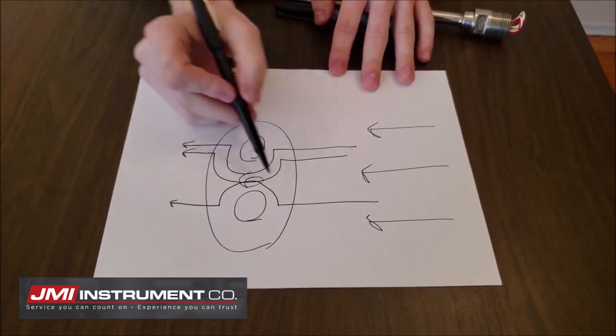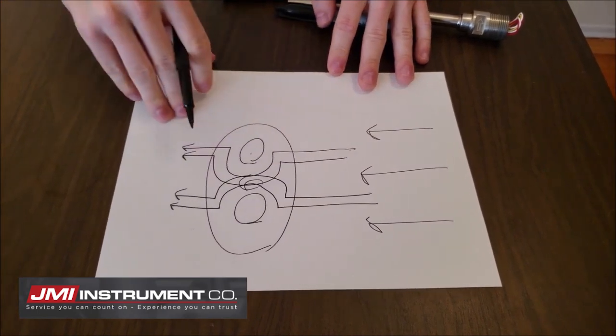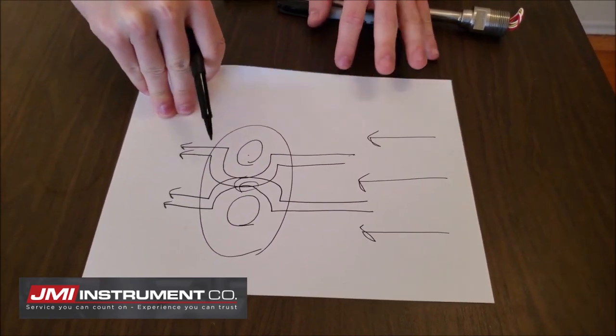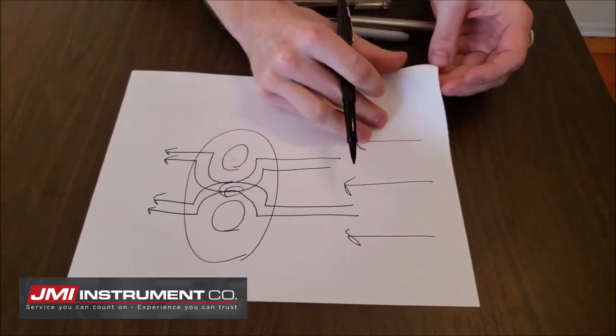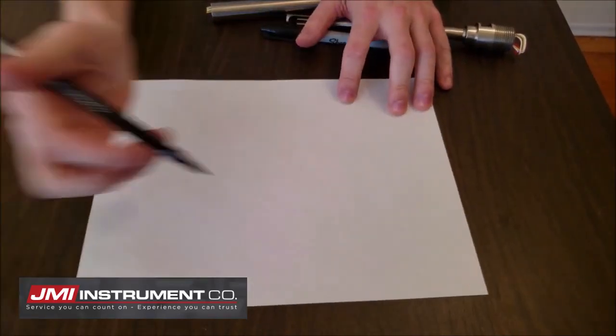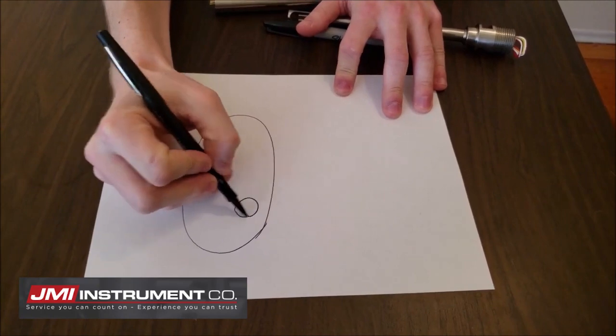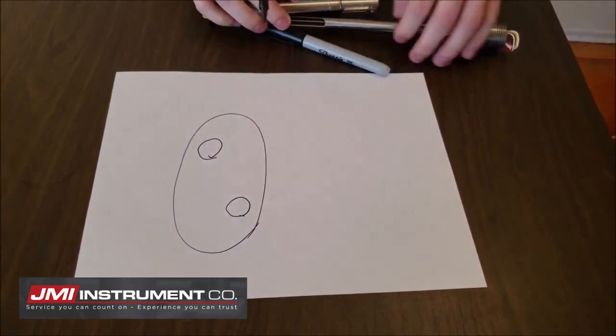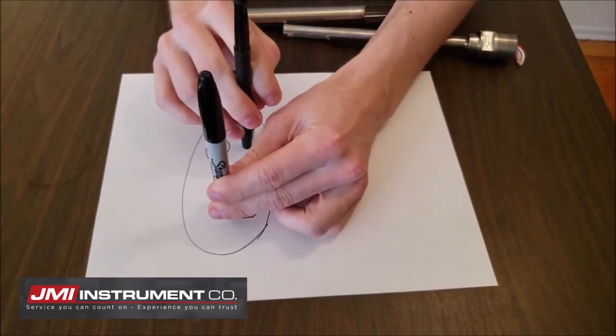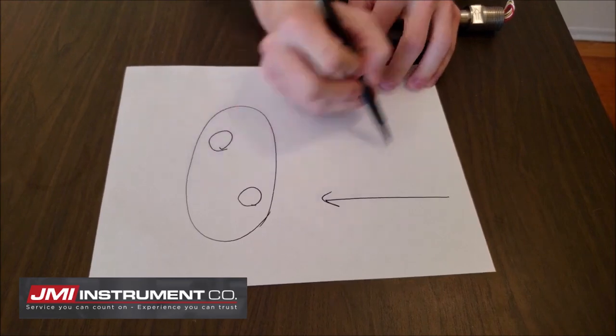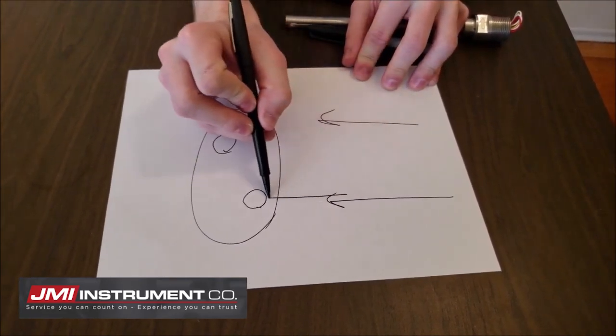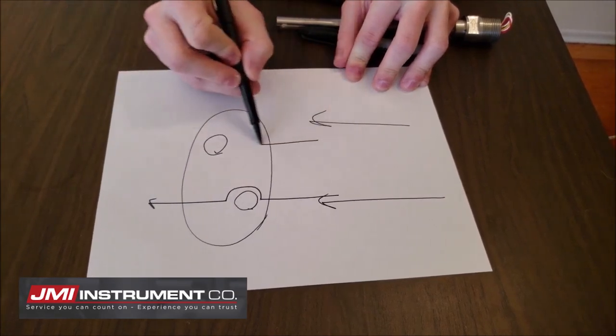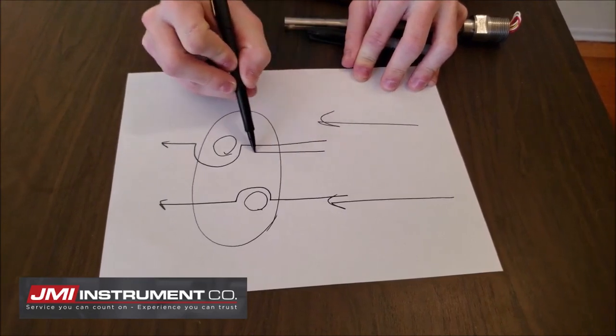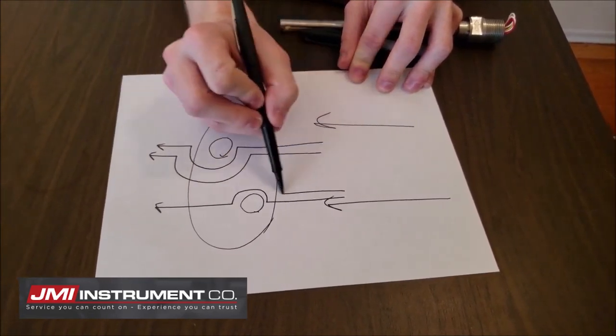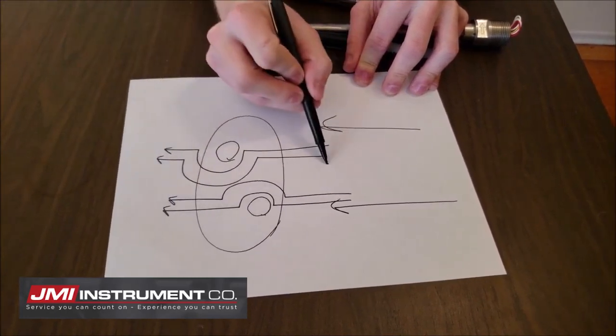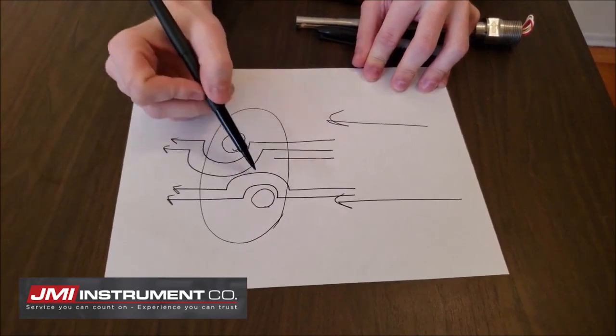Now, Fox Thermal did an analysis on how flow velocity, exactly like this, affects probe stability, and their findings led them to a probe offset of about 35 degrees. They found that to be optimal for both sensing elements for this reason. When you offset the probes, instead of putting them directly in line, put them offset by 35 degrees. So again, same 2 probes, but now they're offset instead of directly in line. See the difference? Take your same airflow, going this direction, and watch what happens. It's going to curve around, and the 2 curves are virtually never going to intersect. This causes for much greater gas flow measurement stability, with the probes being offset as opposed to inline.